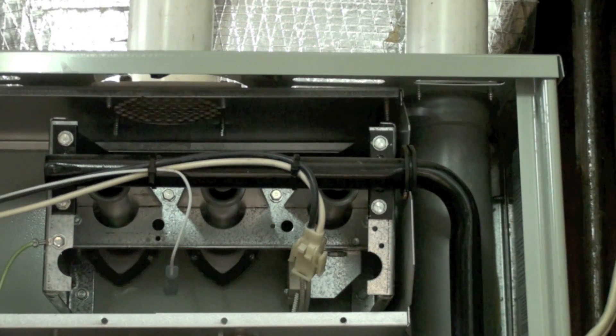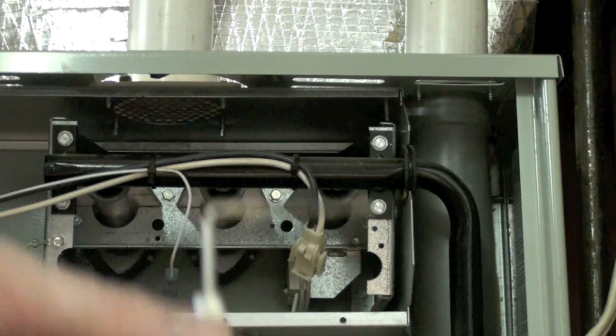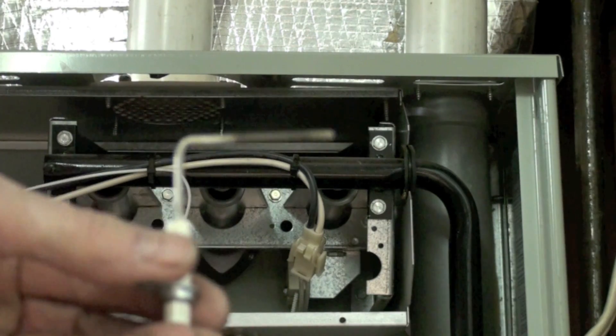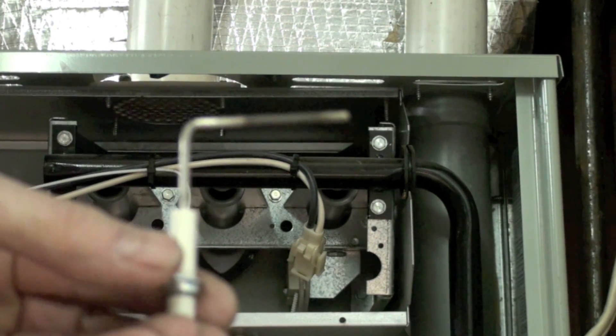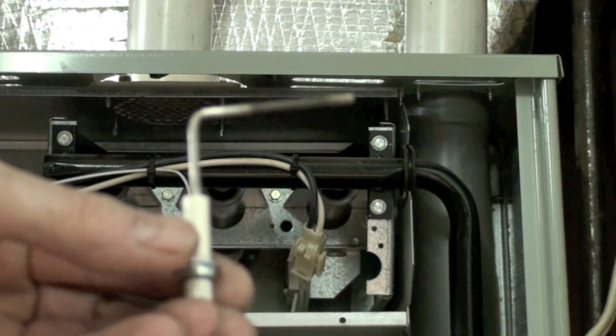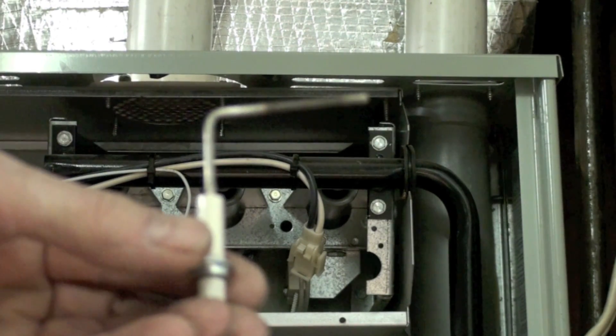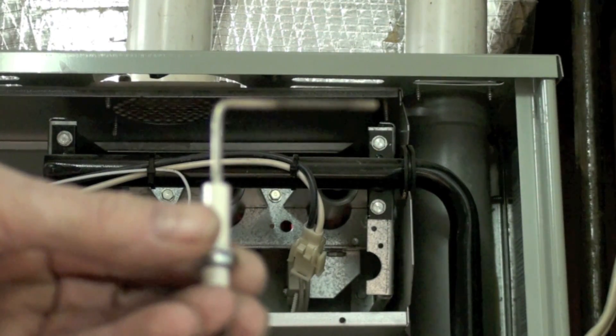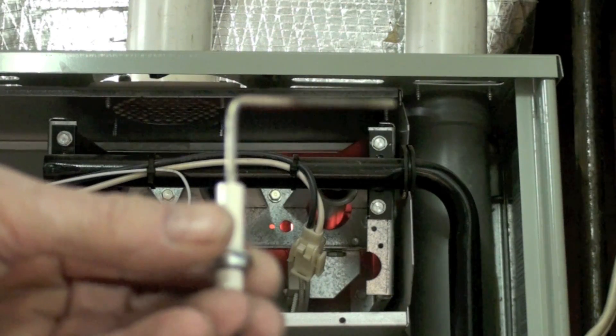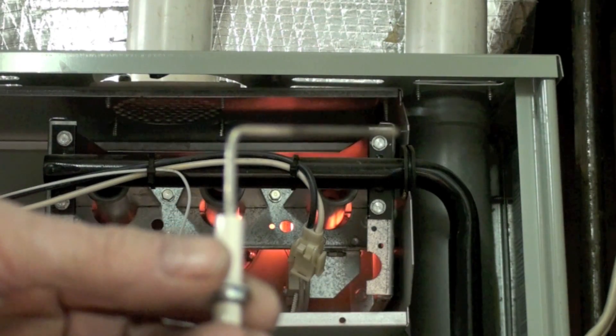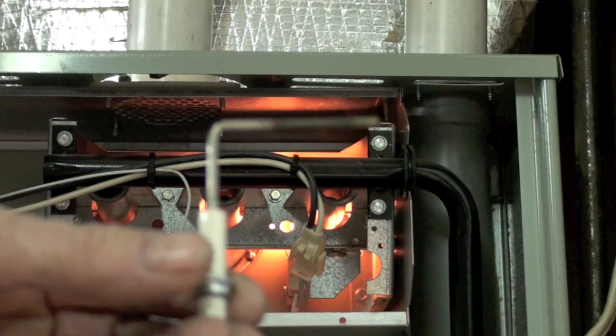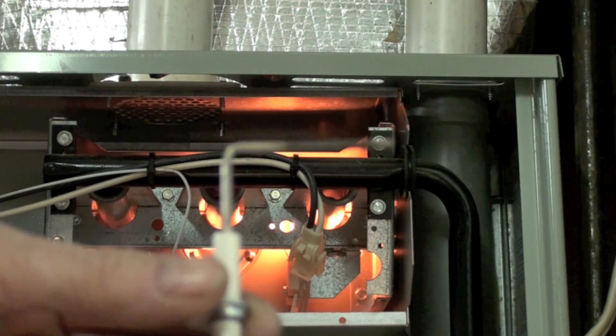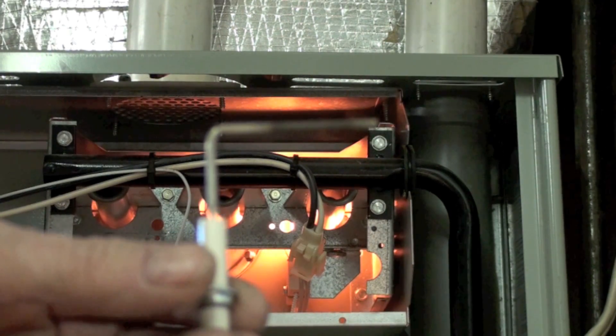Okay, now this is a flame rod. It's not much to look at, but it's just a piece of stainless steel, nothing special. It does get deposits on it. Now this one's been in this furnace for 12 years and I have never cleaned it and it hasn't failed.